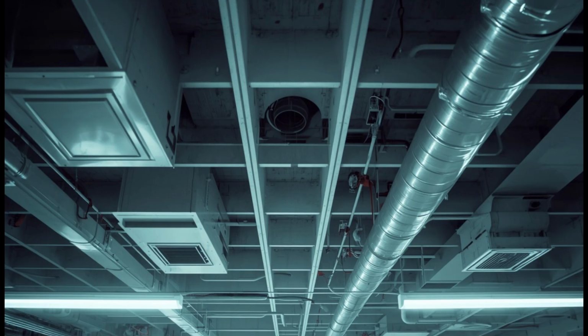The purpose of this small, quiet device is to adjust continuously and independently exactly how much conditioned air enters the particular room it serves. Where the fan and the coils work to prepare a single, shared supply of air for the entire building, no two rooms ever demand precisely the same amount of that air at precisely the same moment. A room facing the morning sun might warm more quickly than one facing away from it. A crowded conference room generates far more heat simply through the presence of so many people than the same room sitting empty. The VAV box exists to account for these countless small differences, opening its damper further when a room calls for more cooling, easing it back when conditions inside settle closer to what the room's occupants prefer.